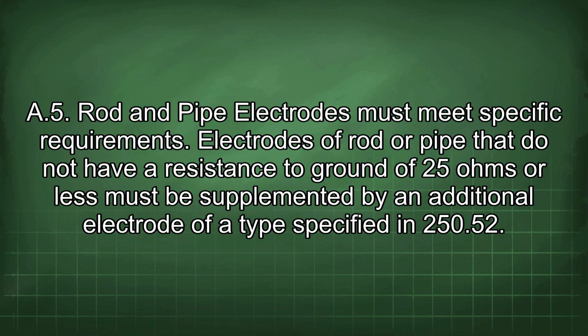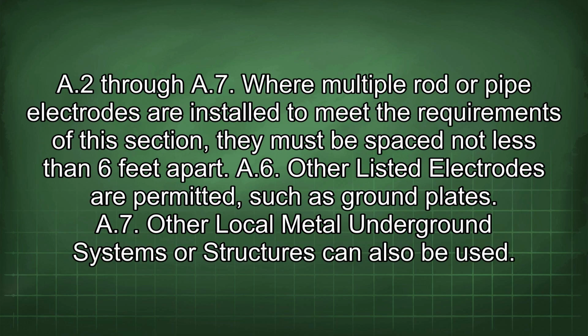Electrodes of rod or pipe that do not have a resistance to ground of 25 ohms or less must be supplemented by an additional electrode of a type specified in 250.52 A2 through A7. Where multiple rod or pipe electrodes are installed to meet the requirement of this section, they must be spaced not less than 6 feet apart. A6. Other listed electrodes are permitted, such as ground plates. A7. Other local metal underground systems or structures can also be used.